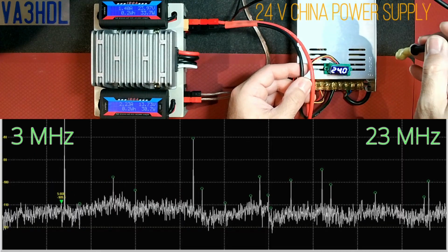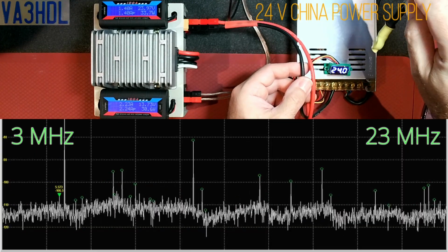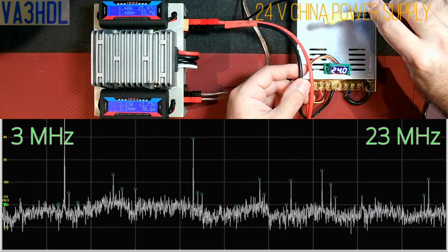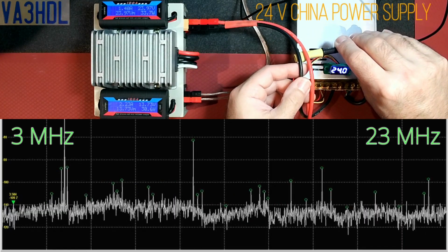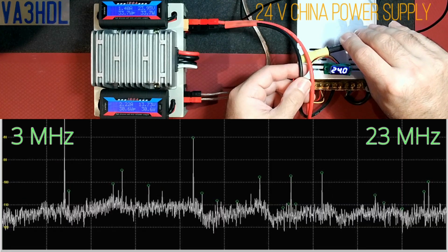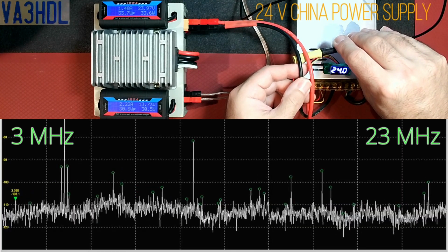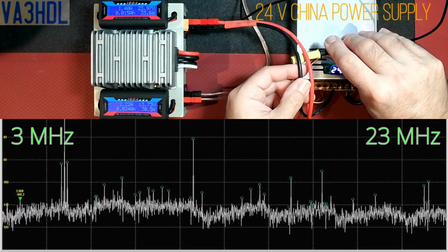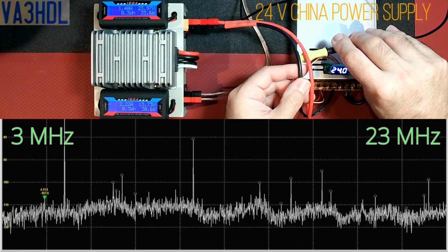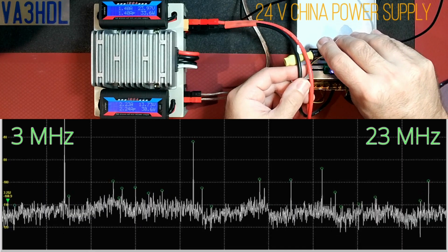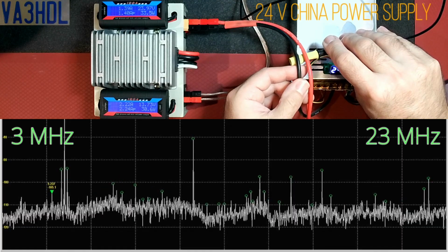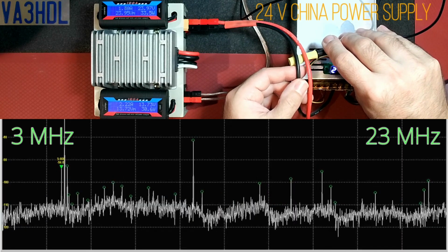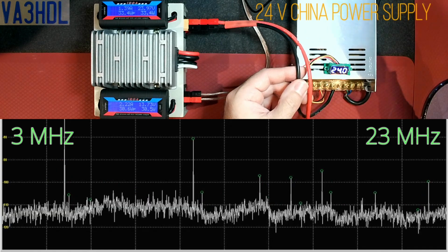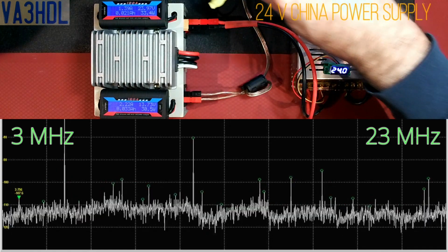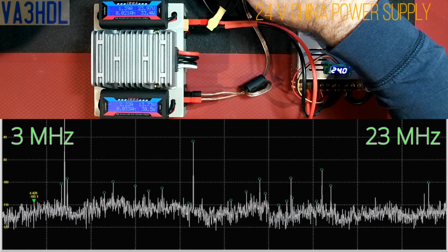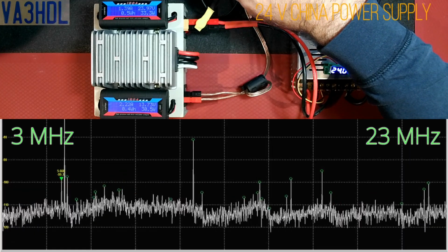There's a clear difference with load. Before we had no RFI, but now with the probe in, we can see peaks of RFI in the same region, around 5 to 6 megahertz. If I remove the probe, it goes away. Let me check here on the input too, same thing.